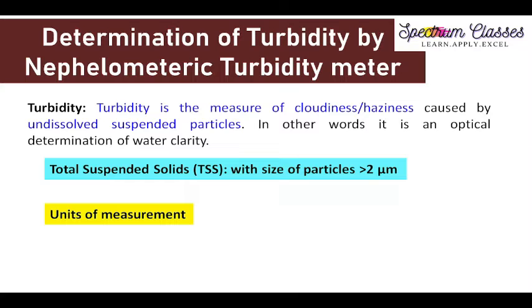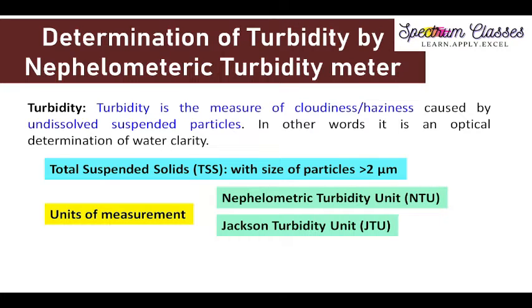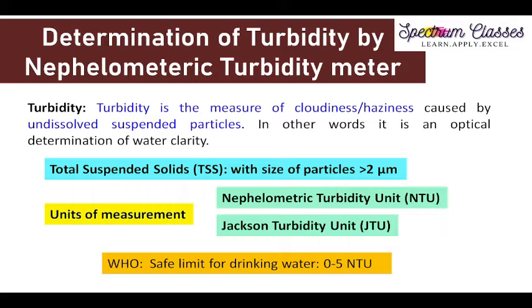Now, units of measurement. Turbidity is measured in two different units: one is nephelometric turbidity unit, represented by NTU, and the other is Jackson turbidity unit, represented by JTU. For drinking water, the safe limits prescribed by the World Health Organization are 0 to 5 NTU. If the water has turbidity less than 1 NTU, then it is ideal. Between 1 to 5 NTU is acceptable, but more than 5 NTU is not permissible.